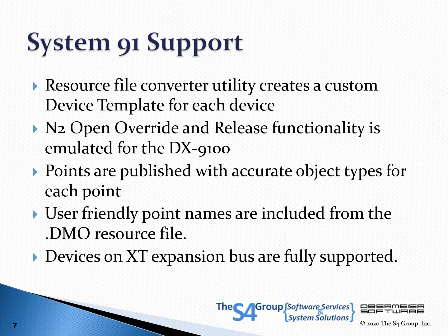DX9100 devices are uniquely programmed for each installation, so the concept of a fixed static template does not work for these devices. The S4 group provides a utility that parses the .dmo configuration or resource file for each device and creates a custom S4 device template that exactly matches the system configuration. This template is then imported into the template catalog and manually assigned to the specific DX9100 that it represents.